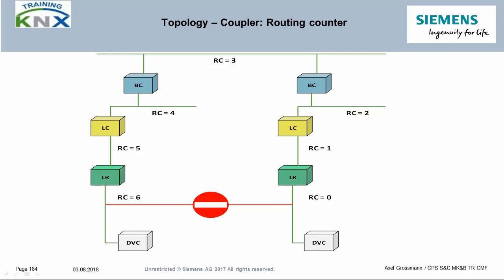Unfortunately, such errors occur more often than you might think. In order to locate them, one must prepare a certain strategy and proceed systematically. First, use the group monitor to see how the routing counter proceeds with otherwise identical telegrams. In the present example of a large loop over six line segments, one would see routing counters 6 and 0 if the telegrams come from the very bottom; one level higher would be routing counters 5 and 1; on the main line 4 and 2; and on the area line you would see two telegrams each with routing counter 3.